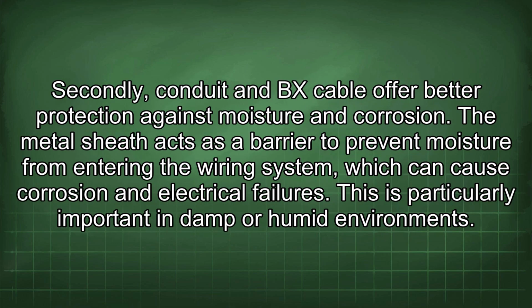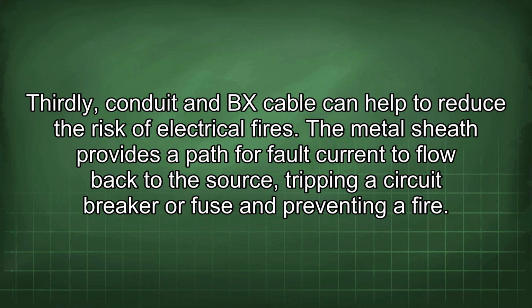Secondly, conduit and BX cable offer better protection against moisture and corrosion. The metal sheath acts as a barrier to prevent moisture from entering the wiring system, which can cause corrosion and electrical failures. This is particularly important in damp or humid environments. Thirdly, conduit and BX cable can help to reduce the risk of electrical fires. The metal sheath provides a path for fault current to flow back to the source, tripping a circuit breaker or fuse and preventing a fire.